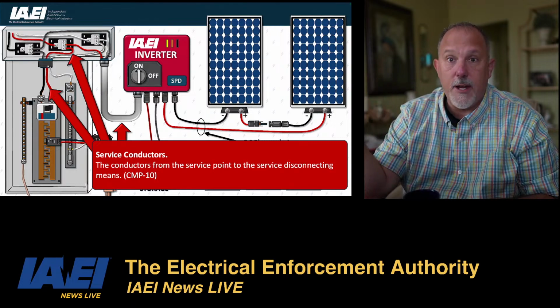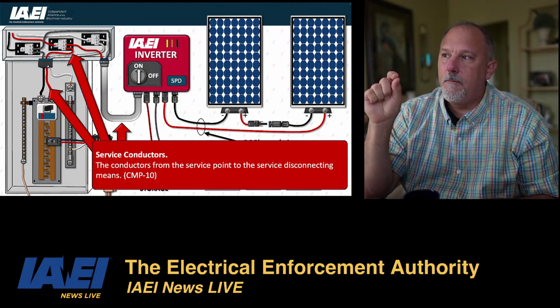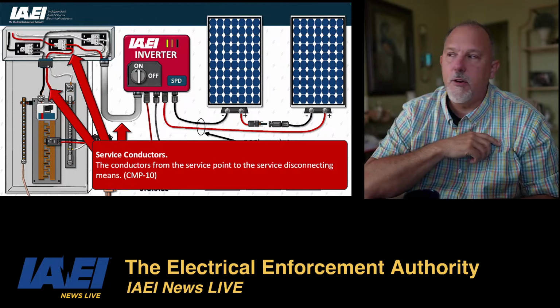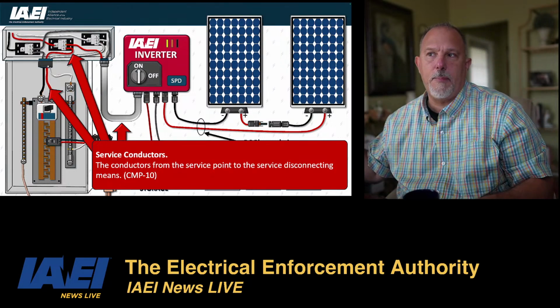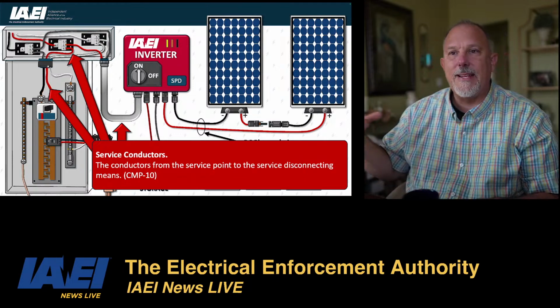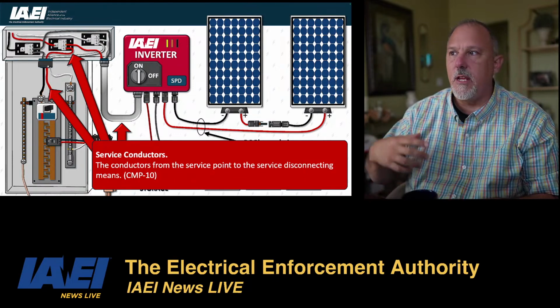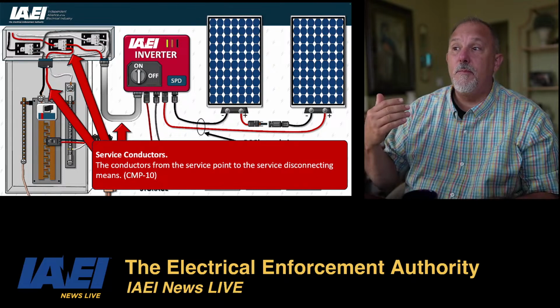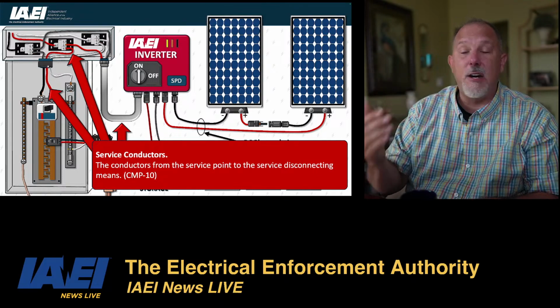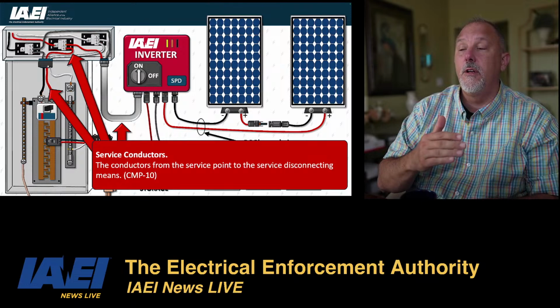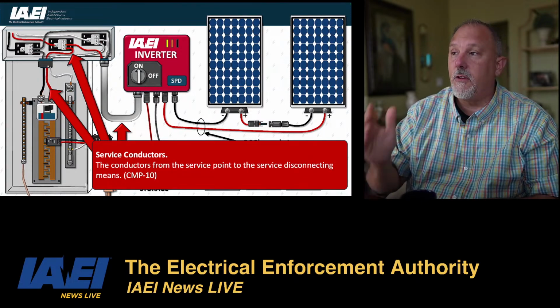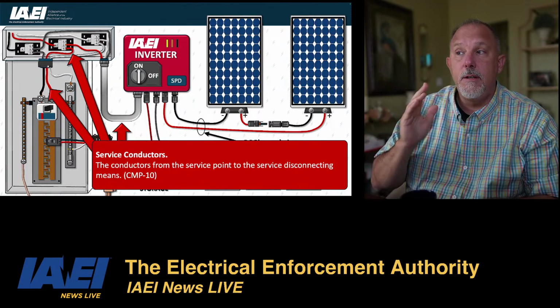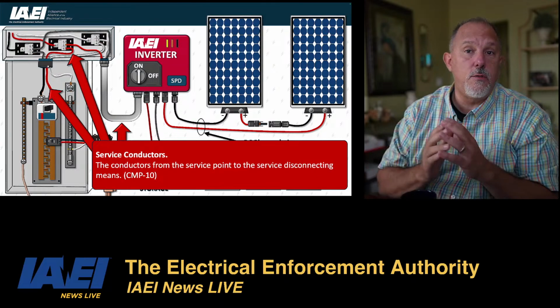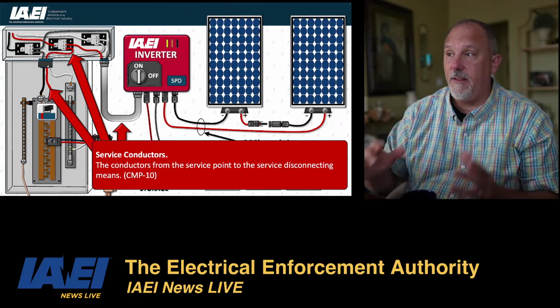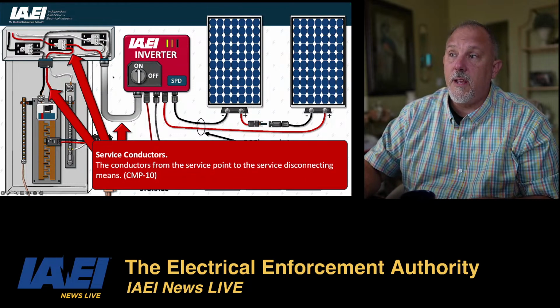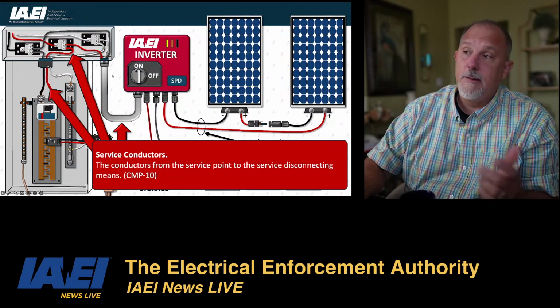Sure thing, Laurel. They may not call those service conductors because, in my opinion, and I think based upon the code language and other people's opinions, the argument I've heard is that the PV system is putting power in, so it's acting like a utility, but it's not owned by the utility. It's a power source. But the challenge with these conductors is not under normal conditions, but under faulted conditions. If there's a fault in that inverter, there's no overcurrent device to provide short circuit protection ahead of that inverter. So we take precautions.